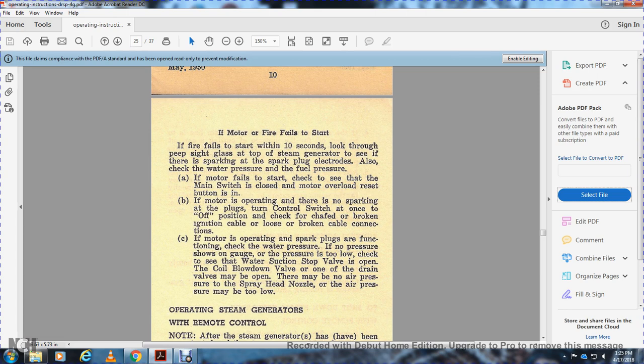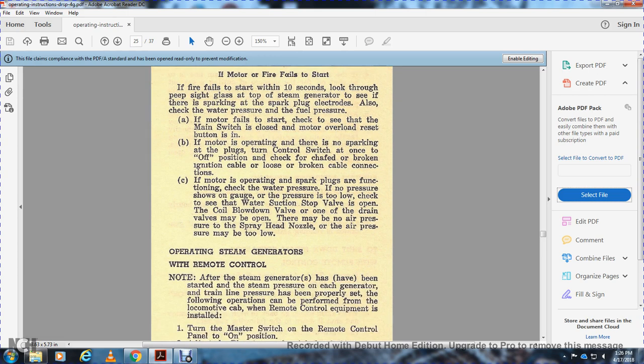If there is no pressure showing on the gauge, or the pressure is too low, check to see if the water suction stop valve is open. The coil blowdown valve or the drain valve may be open. There may be no air pressure at the spray head nozzle, or the air pressure may be too low.